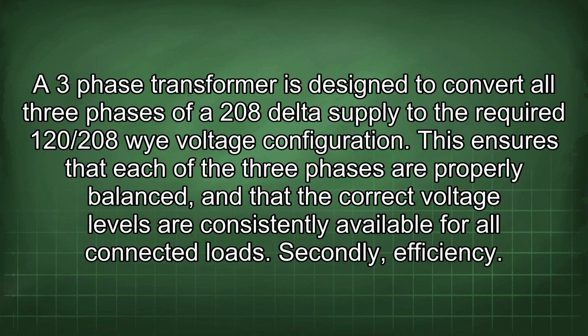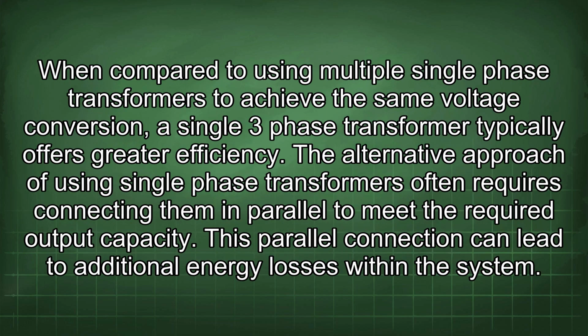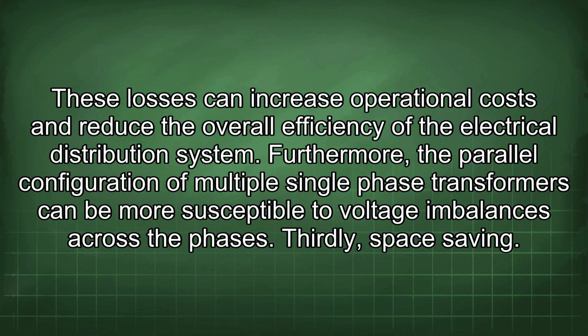Secondly, efficiency. When compared to using multiple single-phase transformers to achieve the same voltage conversion, a single three-phase transformer typically offers greater efficiency. The alternative approach of using single-phase transformers often requires connecting them in parallel to meet the required output capacity. This parallel connection can lead to additional energy losses within the system. These losses can increase operational costs and reduce the overall efficiency of the electrical distribution system. Furthermore, the parallel configuration of multiple single-phase transformers can be more susceptible to voltage imbalances across the phases.